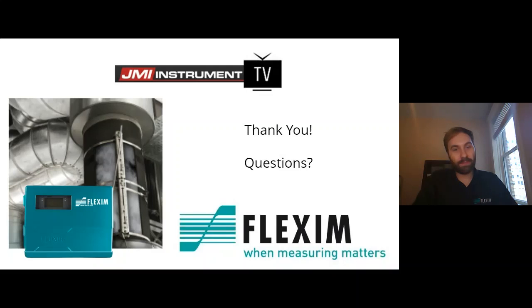Not generally. The only flow meter I've ever heard of that's a two-phase flow meter, which means it measures both the gas and the liquid as it goes by, is very expensive. It's an ultrasonic meter with several sensors. That's very costly. And for us, there's really no way to be able to quantify how much gas is going by. Basically if it's set up to measure liquid, we're really only going to see the liquid that's going by. Or if we're set up for gas, we do have something called a wet gas compensation, where if you know the LVF of the gas, then you can actually program that into the meter, and it will subtract the liquid from the gas measurement. So you'll get a true volume flow of gas minus the liquid.